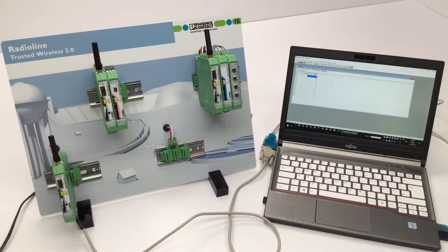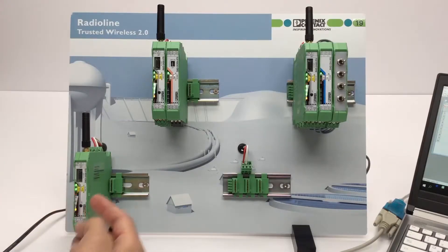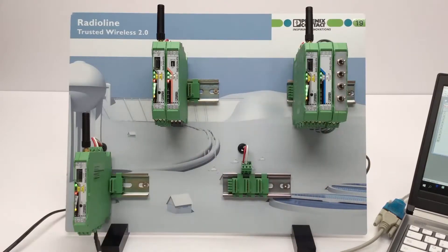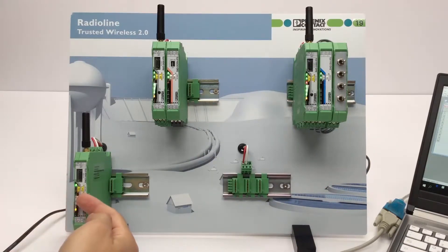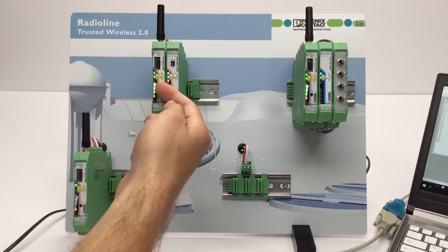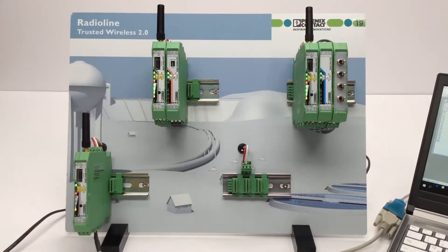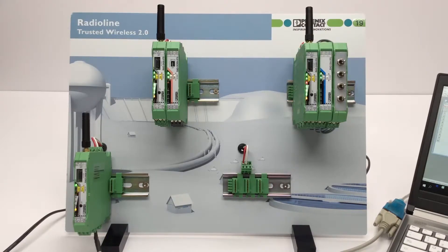As soon as the demo setup is supplied with power, the radio connection will automatically build up within a few seconds. The red ERR LED on the radio module flashes until the respective I/O modules have been addressed via Modbus communication. The flashing ERR LED results from a watchdog contained in the radio master. This watchdog monitors the Modbus communication and is triggered with each correctly received Modbus telegram. The watchdog timeout can be set between 200 milliseconds and 65 seconds.